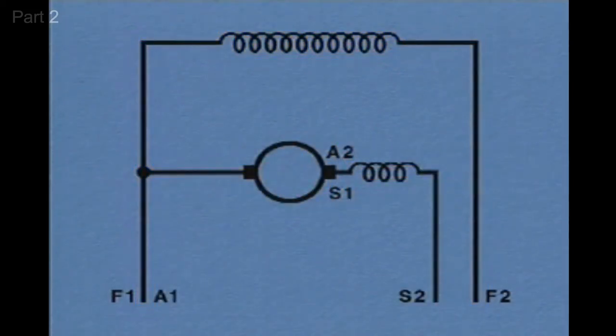Now this is a schematic of a typical compound motor. Compound motors are the most commonly used type of DC motor and they are also the most complex because a compound motor contains two types of fields: a series field and a shunt field.